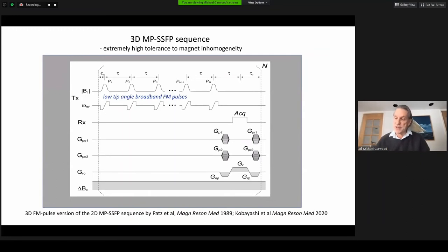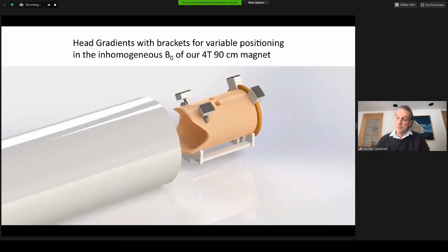Here is one pulse sequence we will use to perform MRI with extreme magnetic field non-uniformity. It is a 3D version of the missing pulse steady-state free precession sequence developed by Patz et al. To demonstrate its tolerance to field inhomogeneity, we modified a standard head gradient set so that it could be mounted far from the isocenter of our 4-Tesla magnet where the field is rapidly dropping off.